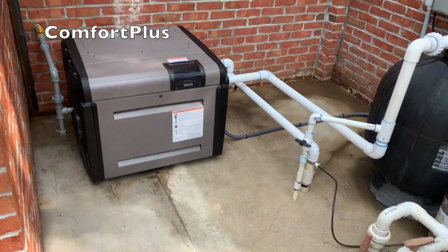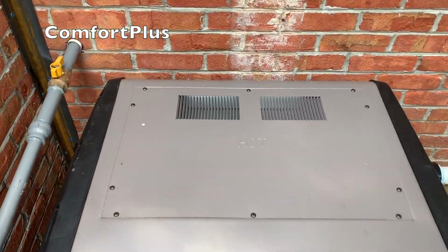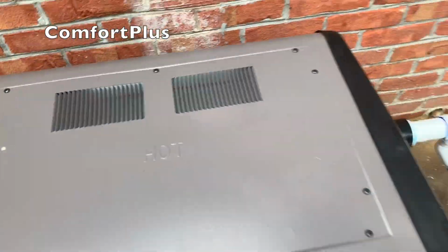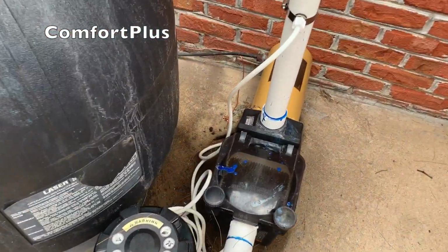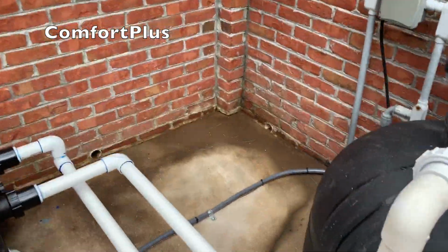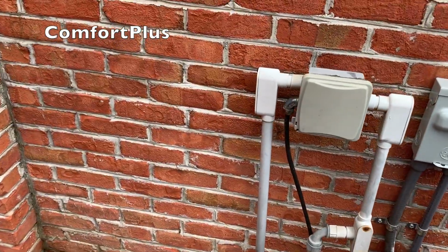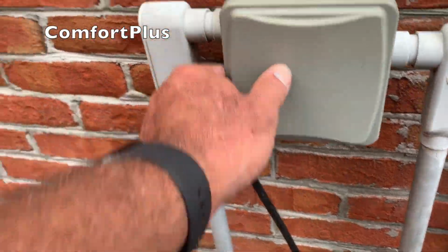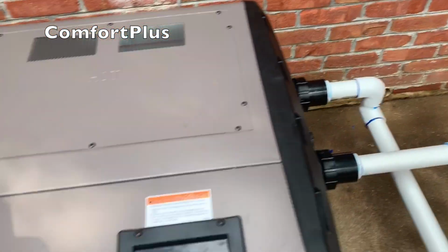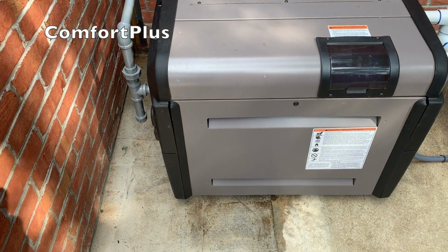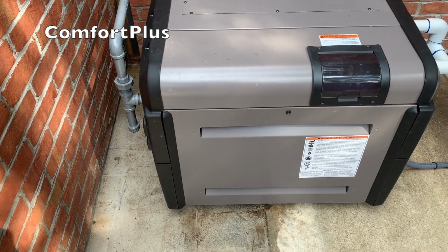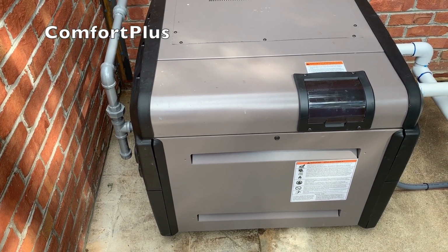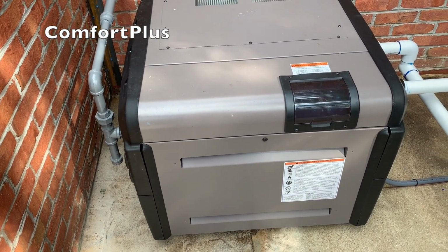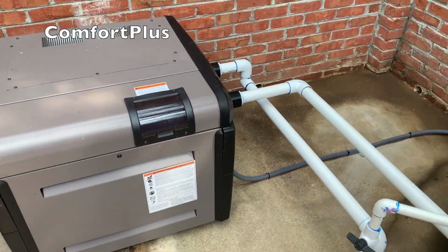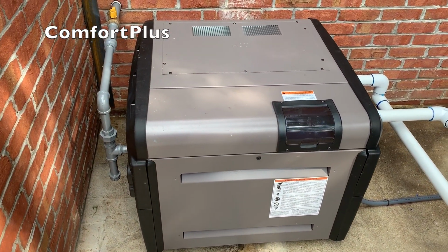Okay, final product. It's running right now. Maybe the camera will pick it up. If you're standing outside, it's really no different than the pump running. I've got to come back. I don't have anything to secure this to the wall. I'm going to put a piece of unistrut down here and strap that down good and tight. And when I come back, I'm going to go ahead and check the gas pressure and everything. Like I said, I clocked the meter and it's the right BTU, so I'm sure it's probably set correct from the factory, but I'll check it anyway. I'll probably come tomorrow and do that. But it's 90 degrees out here, and I got some no cool calls to do.